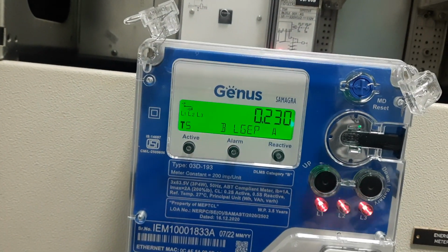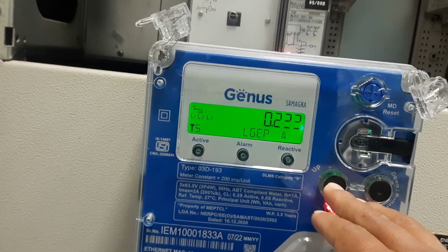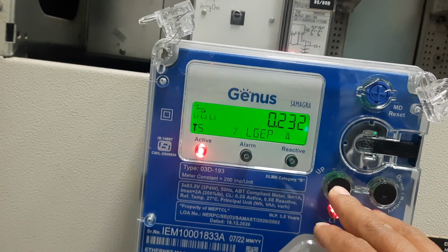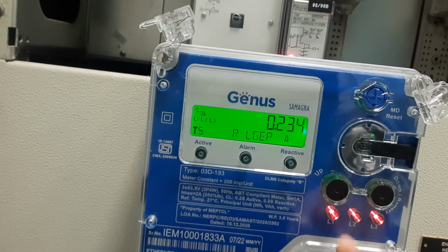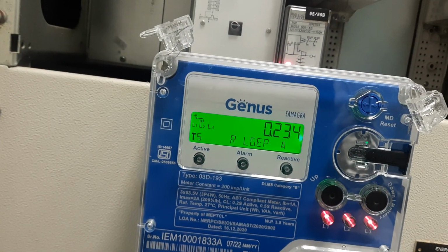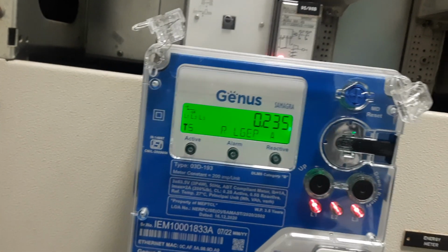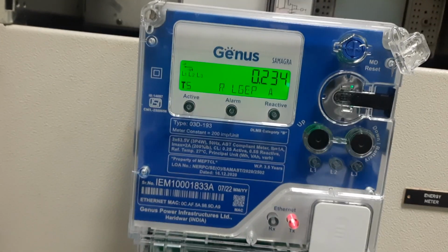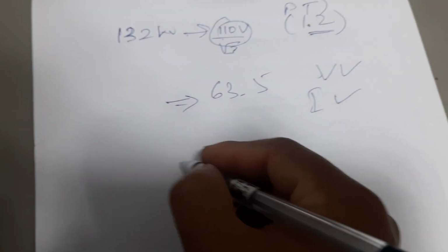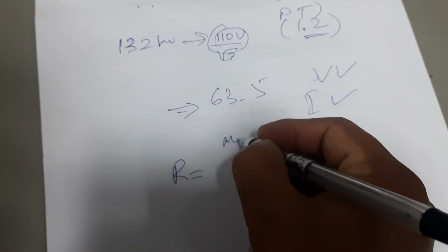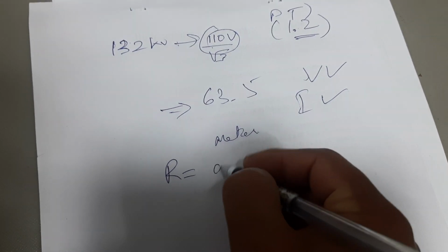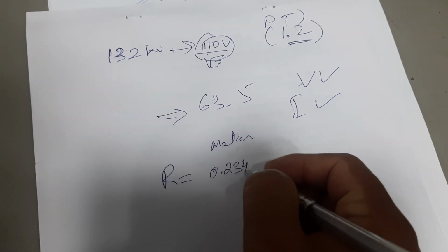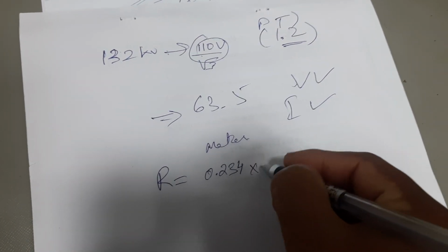Current, okay, this is B phase current will be 0.230 and Y phase is 0.232 and R phase is also more or less the same, 0.234. Okay, let us take this value 0.234 or 0.235, 0.234. Okay, let me take 0.234 of R phase. Okay, if this value of R phase in the meter is 0.234, all right, then I'll have to multiply with the CT ratio.